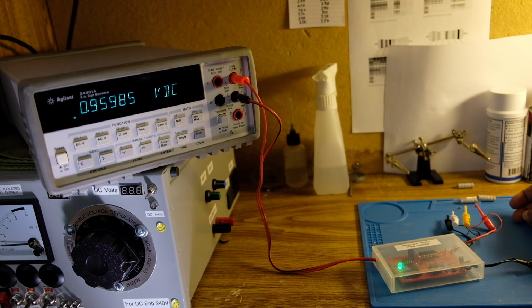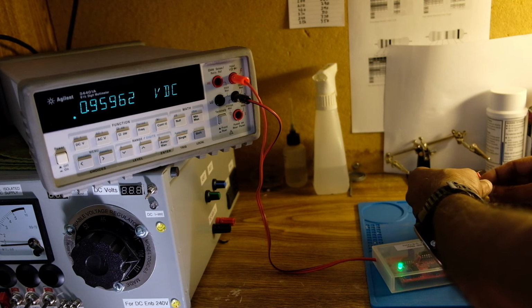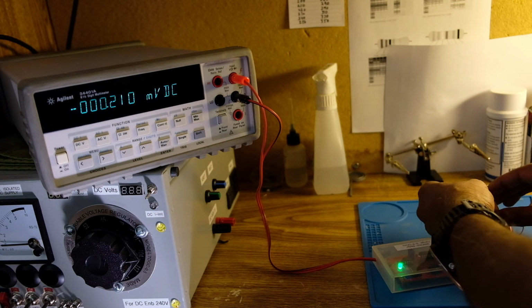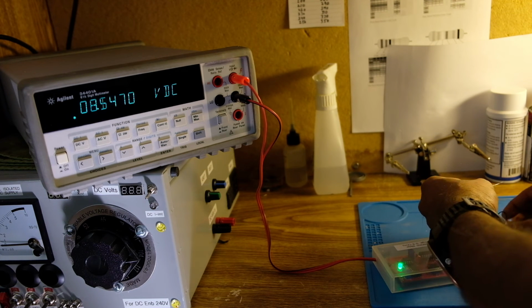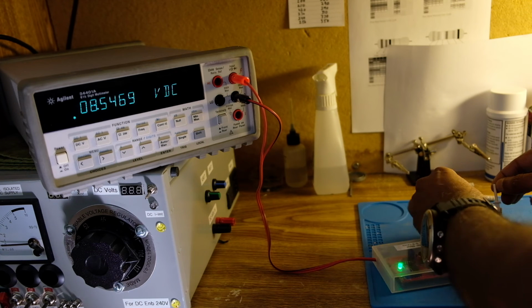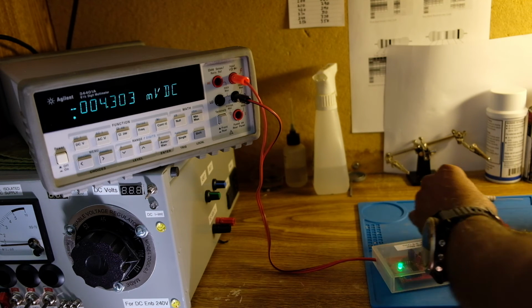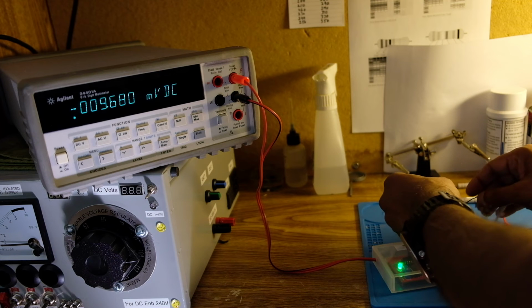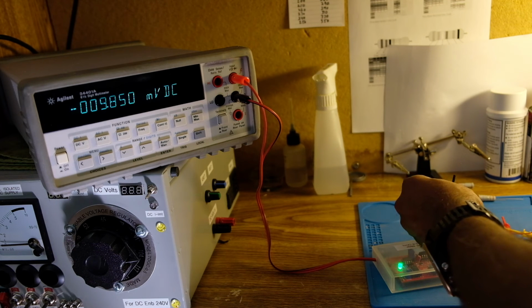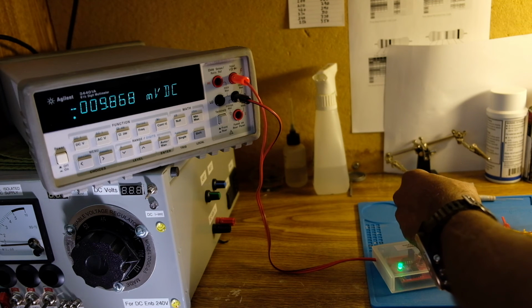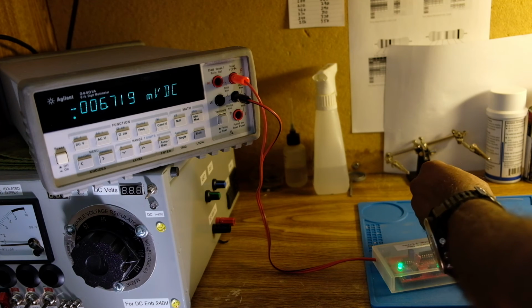Ideally this will be used to measure very low resistances, typically conductors that carry high currents, so the self-heating effects will be fairly small. But with very small components, you're going to see some heating effects. Unfortunately, using 100 milliamp current, that's what you get. That's one of the disadvantages, but at the same time you have better noise performance and less gain required, so that helps.